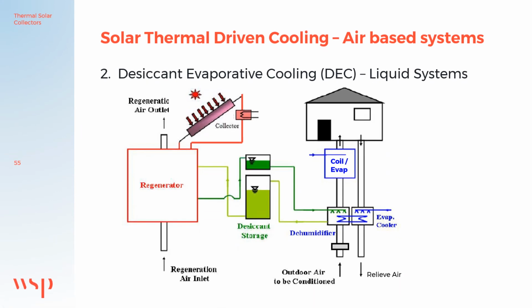Another variation of desiccant evaporative cooling is the liquid systems, which are very similar to the air systems. However, they use a hygroscopic solution to attract water from the air and gets diluted and is regenerated afterwards using the free heat from the solar collector. I know it sounds complicated, but there's a diagram that illustrates the principle.